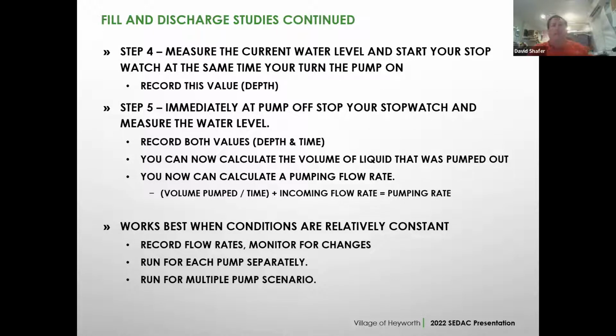You're going to do the same thing again, but pumping down. If you have a second person to help you, it's a lot easier to have someone put the pump in hand and pump down, versus trying to guess right when the float's going to trip and do your time and depth measurements. You measure your two depth values and your time, and you can calculate the volume of liquid that was pumped out. Your pumping rate is the volume pumped out divided by the time it took, and you add your incoming flow rate to that, because while you were pumping out, you still had flow coming in.